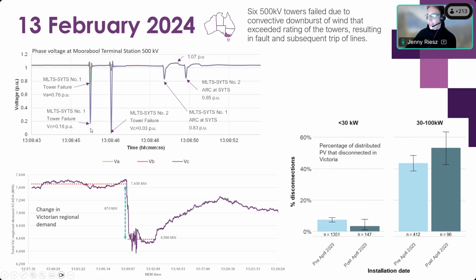And of particular interest to us in dealing with distributed PV and load behaviours, we saw some very low voltages recorded in the Victorian transmission network, down below 0.2 per unit. And this is the measurements of total regional demand for the total Victorian region. You can see a very significant drop in demand. We lost almost 1 gigawatt of load that we believe disconnected. And this is probably the most significant loss of generalized load that we've seen. So a lot of our efforts are in understanding shake-off of distributed PV, but we also need to understand the shake-off of load that occurs in these same events so that we can then model how the two of those interact in these power system events. And load shake-off is considerable in the sorts of events that we're looking at.